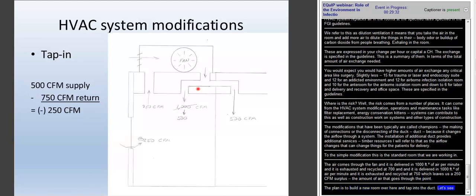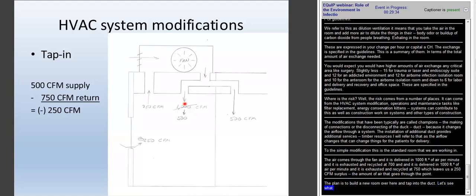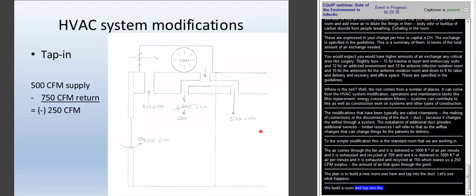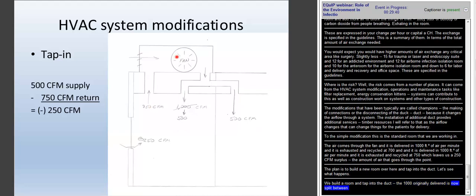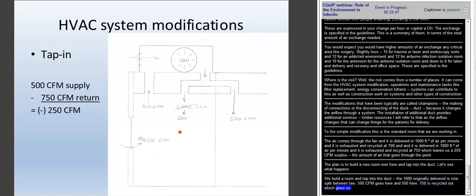Well, that 1,000 that was originally being delivered here is now split between two. So 500 CFM is going in here, 500 is going in here, 750 is being recycled out, which gives us a net deficit of 250 CFM, and this room ceases to be positively pressurized and now becomes negatively pressurized.